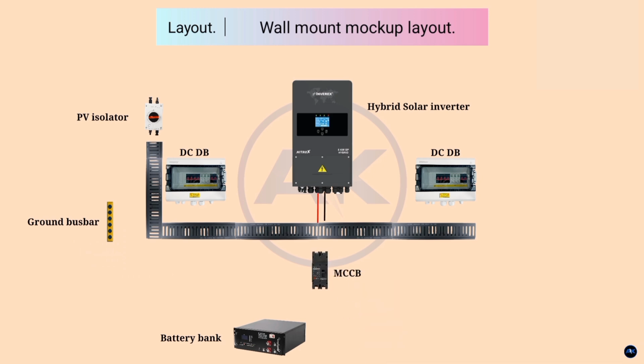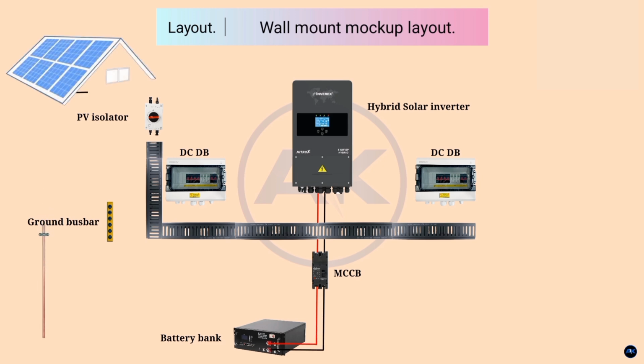Then you can connect the MCCB to the hybrid inverter and then to the battery bank, followed by our PV isolator switch. Connect that and then to the PV array. And of course, all the ground wires go to the bus bar and then from the bus bar to the ground rod. Now we have our AC output from the inverter and the AC input to the inverter, and we have to ground the chassis of the hybrid inverter, connected to the bus bar.